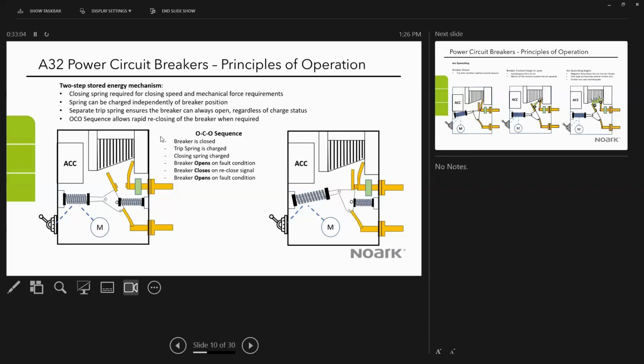So the principle of operation for an air circuit breaker is called a two-step stored energy mechanism. It starts with the closing spring. The springs are very large and very powerful, and that's required because you need a very fast operation in order to close and open the contacts and reduce the arcing that happens. The spring can be charged independently of the position of the breaker. So at any point in the operation of the breaker, the spring can be charged.